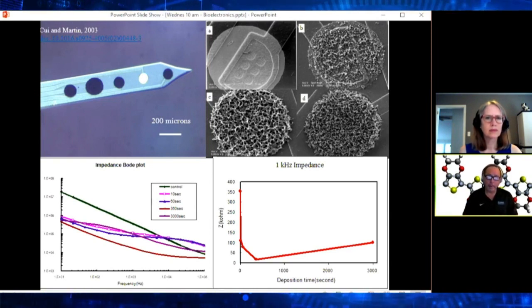Now, the reason that's so important is that impedance controls the energy requirements, meaning the battery lifetimes, the sensitivity, the voltages, the safe operating window that you can use. So many, many properties of biomedical devices are critically related to lowering the impedance. And in fact, if you want a really tiny electrode, which is what you want if you want the more precise local ability to talk to or listen to cells in the body, the very small electrodes have always been very difficult to manufacture because if they're flat metal electrodes, they always have a very high impedance. And so this technology provides a way of making very low impedance, very tiny electrodes that can significantly improve the precision and performance of these devices.